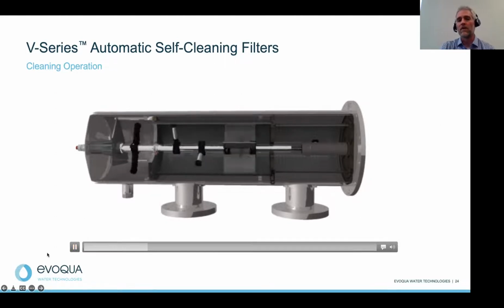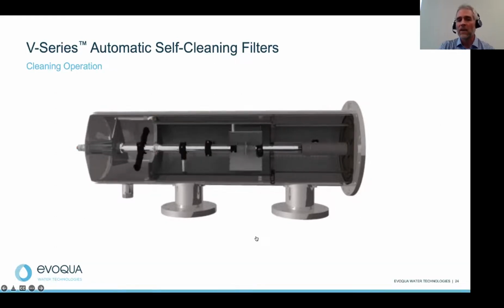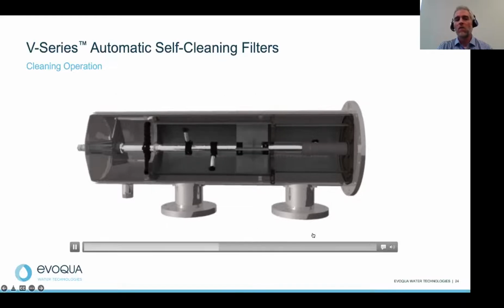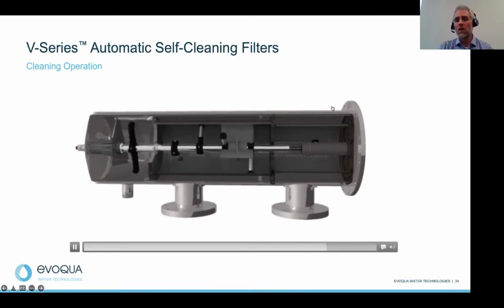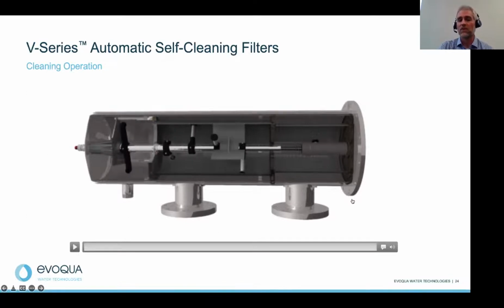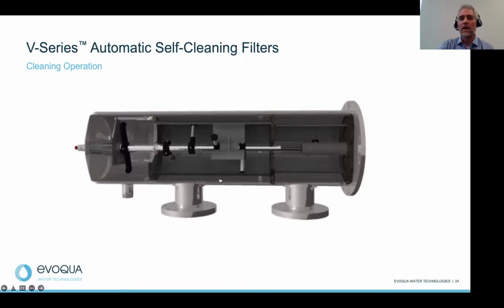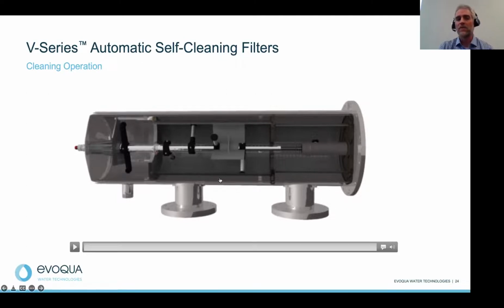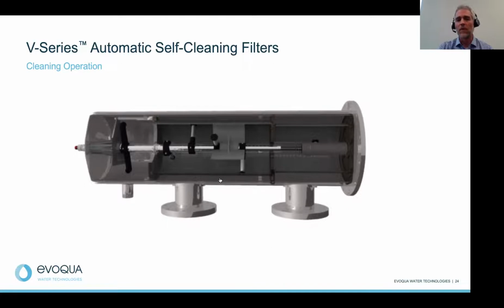on the other end. Again, no need for any additional penetrations for limit switches or any types of gearboxes, right? This is fully enclosed, only with one flange on one side for operations and maintenance. The screens itself need to be changed out on an annual basis, or depending upon the loading and operation of your tower.